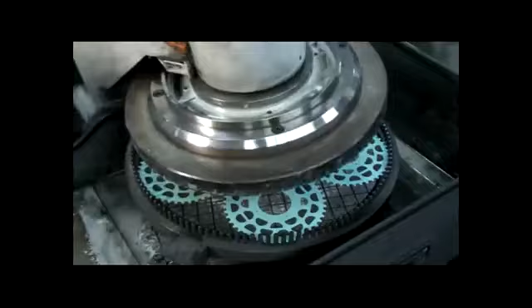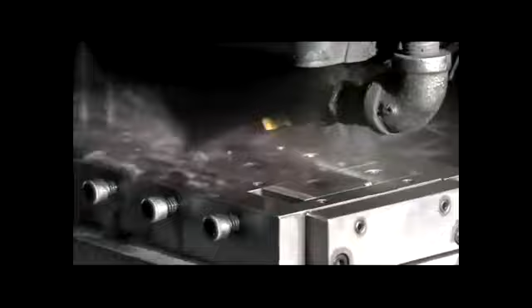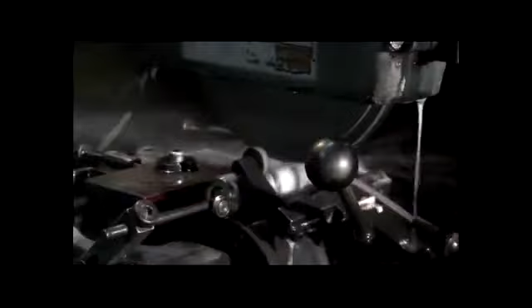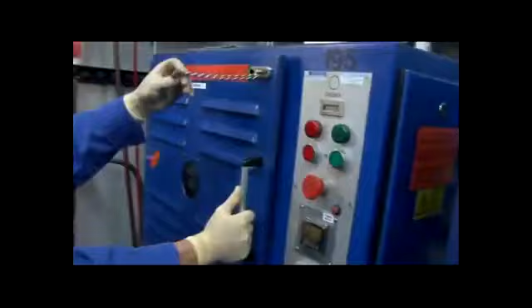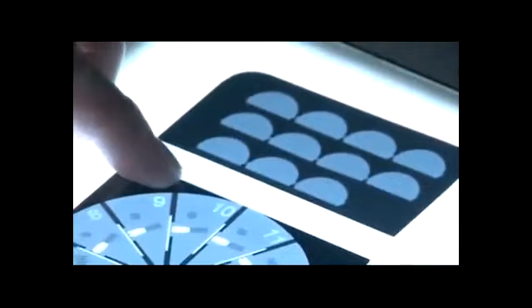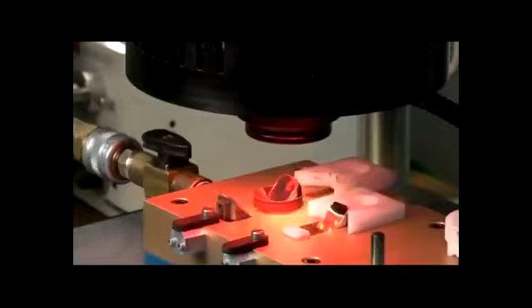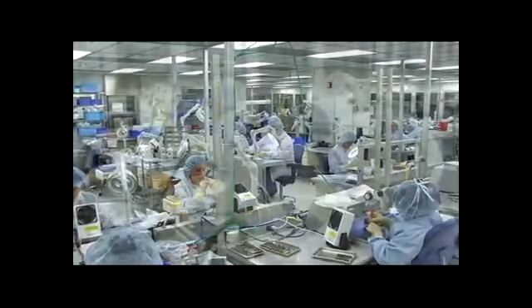The parts are machined again after the coating is applied. Because of the high durability of the components and the requirement to reduce reflection and heat buildup during the cutting, the process utilizes high-pressure coolants and diamond tooling. Next, a mechanical polishing operation removes any slight surface imperfections and provides the final finish for which St. Jude Medical mechanical heart valves are so well known. After completion of the initial operations, there are many workstations where each valve is 100% inspected to rigorous St. Jude Medical specifications. 100% microscopic inspection for visual defects, 100% X-ray inspection for internal component and coating defects and coating thickness, and 100% dimensional inspections to ensure precise matching of individual orifices to dimensionally compatible leaflet pairs. In our final controlled area, the parts are again inspected 100% visually under a microscope and computer matched for the best dimensional tolerances and fit.